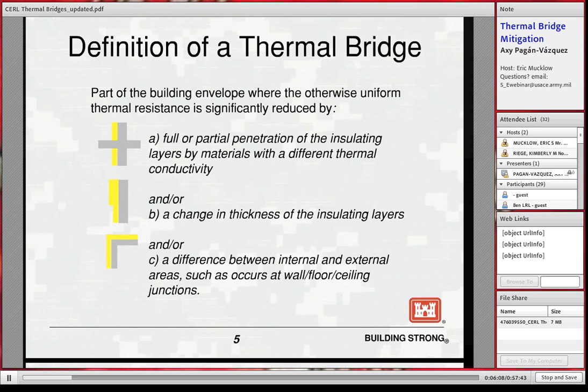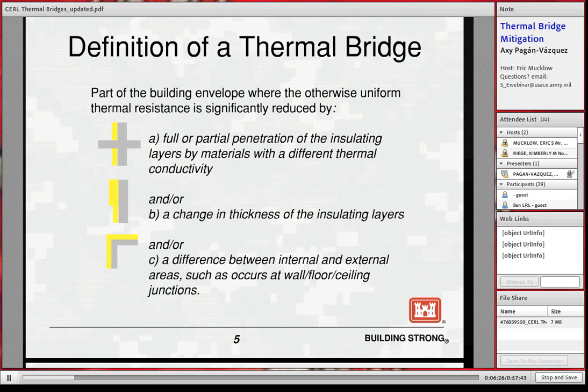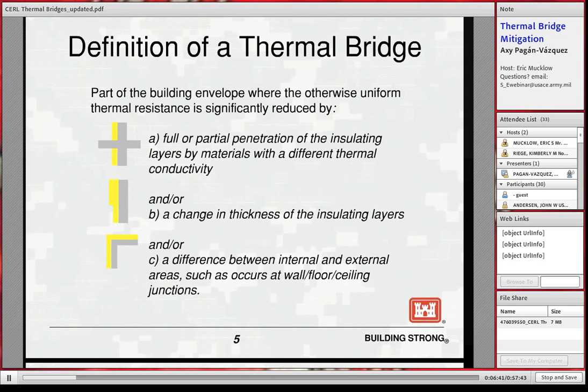So, by definition, what are thermal bridges? Essentially, they are building envelope localized regions that possess a high heat transfer rate compared to their neighbors. This usually happens in building envelope locations where apparently high thermal resistance is bypassed, as we saw in the previous picture. Thermal bridges mainly develop where: A) a highly thermally conductive component penetrates the envelope insulation layer; B) when there's a change between insulation layer thicknesses; and C) where there's a difference between geometries of the building envelope surfaces, such as a corner of a wall.